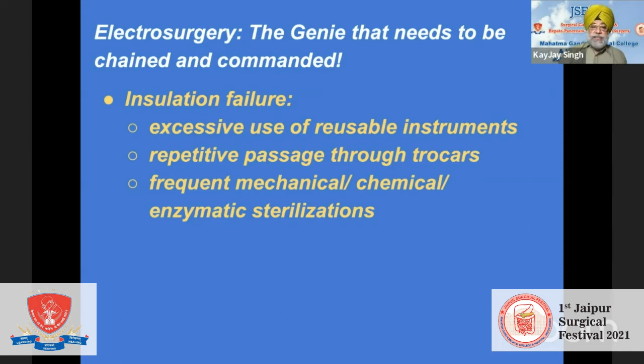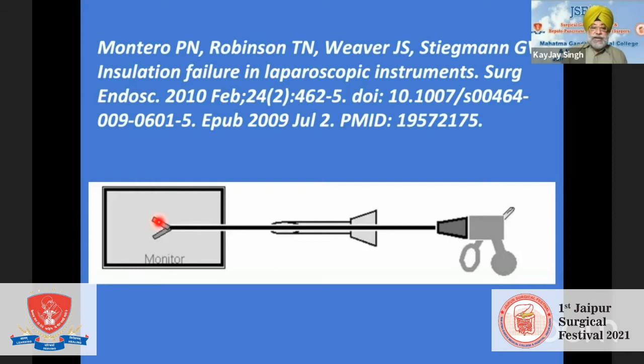This study demonstrated the structure of a laparoscopic instrument that is delivering energy of the electrosurgical unit here. It's got 4 parts, and zone 1 is that part which is visible to the surgeon. Thankfully, most of the breaks of insulation happen in this area, which are visible. So the surgeon will avoid or get the sheath changed. The second zone is the most tricky zone. It is not visible to the surgeon. It's outside of the monitor view and outside of the trocar also. And it has been estimated that 18% of sheath failures of insulation happen in this zone. And if you use such an instrument to deliver the energy, you're heading for a disaster.